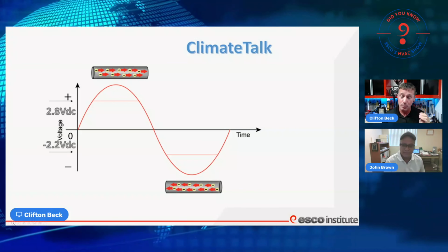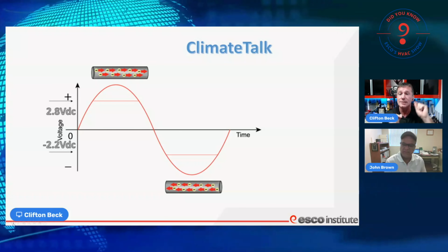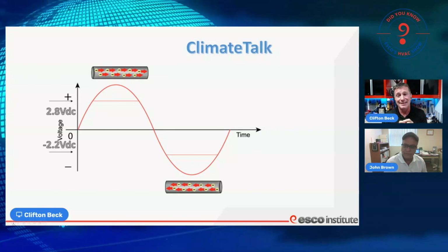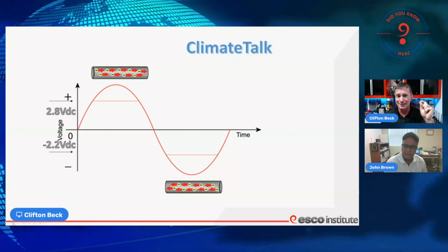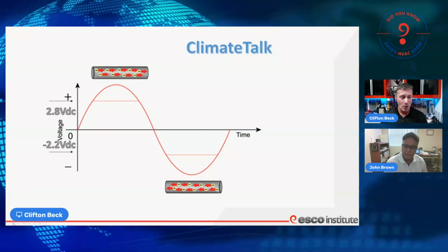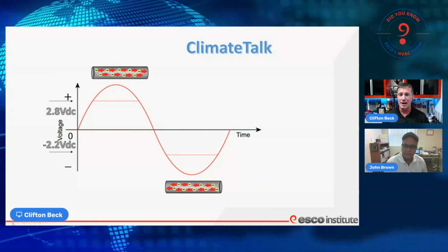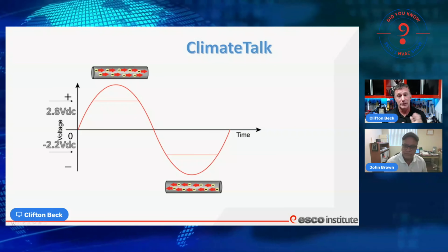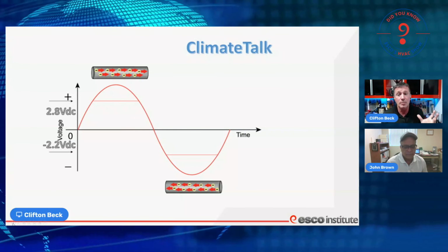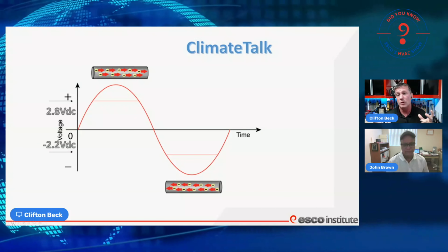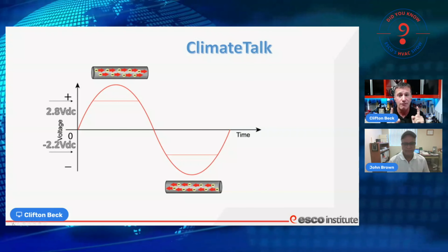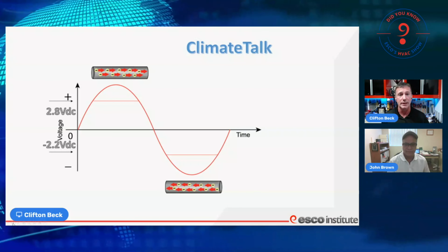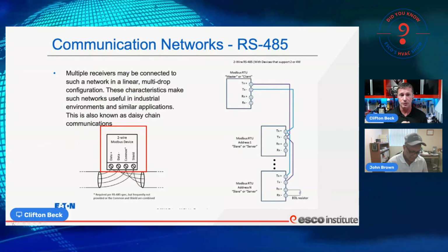So what we end up with in those 2 points is a 5-volt DC signal that is partially positive in reference to ground and partially negative in reference to ground. So now we have a place that we can start. Well, when we talk on that, we're not going to be able to listen in on what's being said on that, but we can verify if our network is working properly so that we can start looking for issues, right?